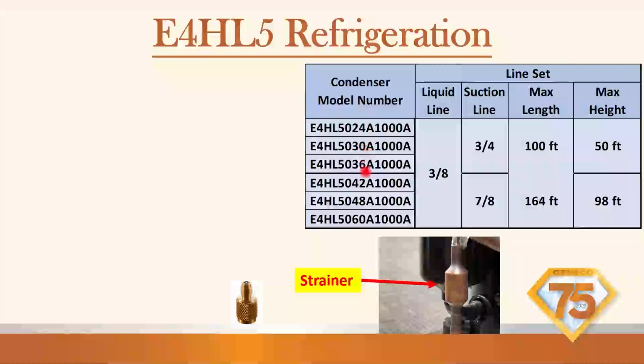Our 2, 2.5, 3 ton is 3/4, 3/8. 3.5 to 5 tons is going to be 7/8, 3/8. Max length is 164 feet on the 4 and 5 ton. 100 foot, so that's something to keep in mind. It's only rated, and these are not in the piping program, by the way. If anybody takes advantage of those piping programs, they are not in the piping programs on comfortsite.com or ASDealerNet.